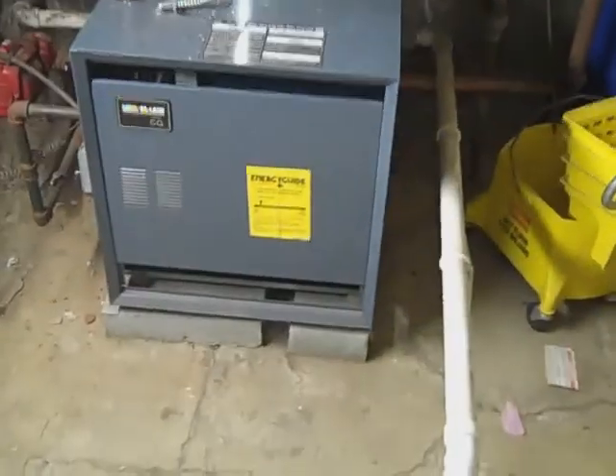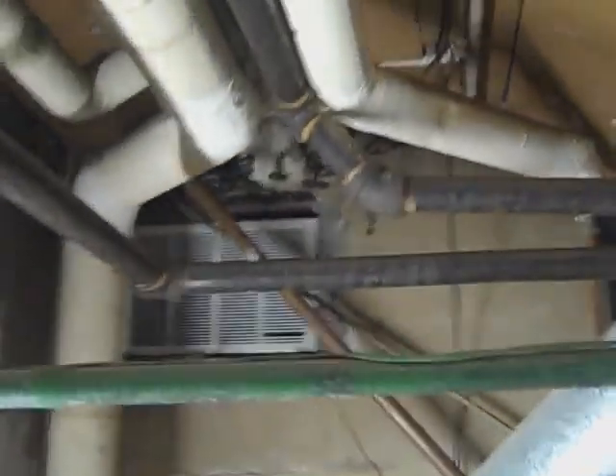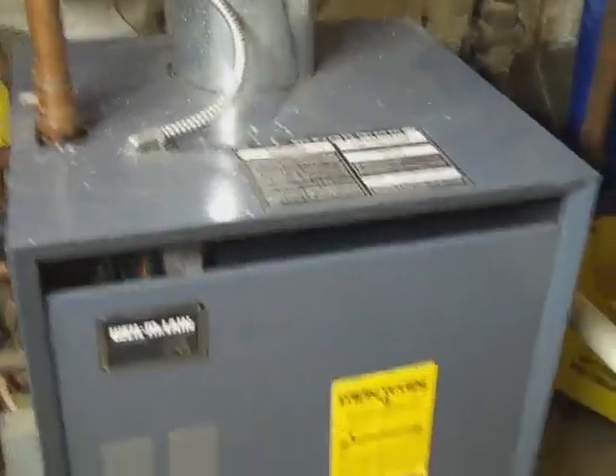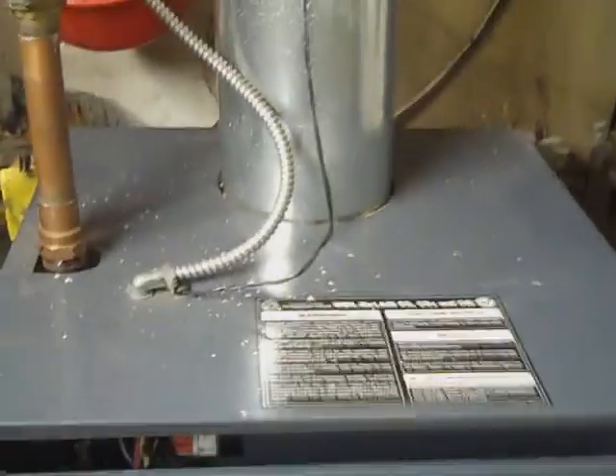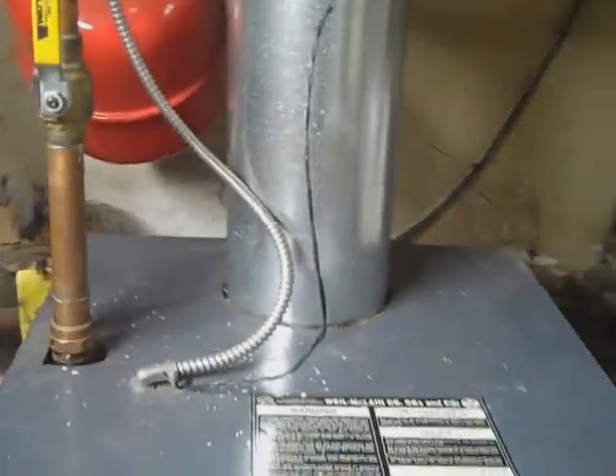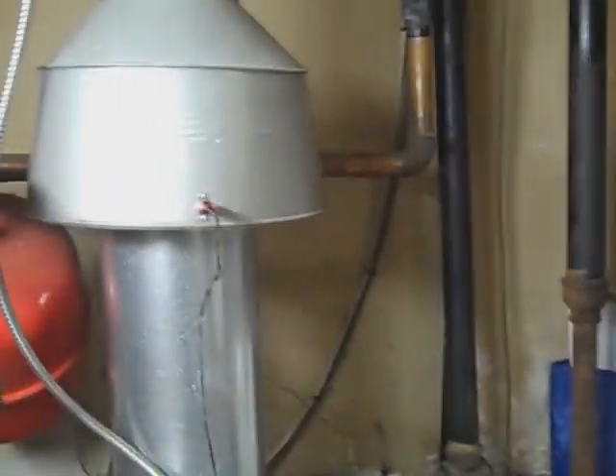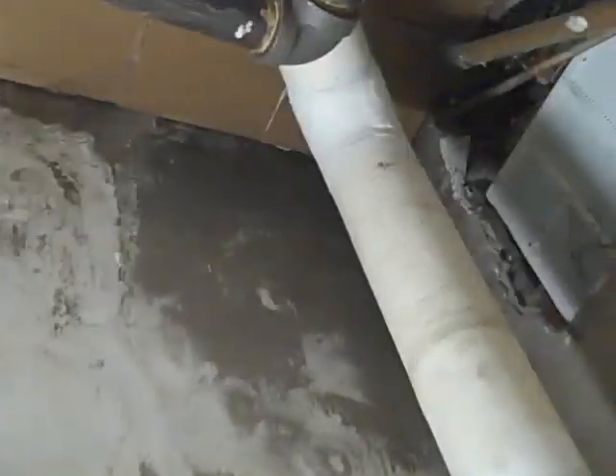You can see there's the boiler. Above the boiler, this is a vent. This vent is actually needed for the HVAC system. See, above the vent there are also holes. What this boiler needs is really controlled ventilation, not uncontrolled ventilation, which is what it's getting right now. So determine how much air it actually needs, get a pipe in here with a fan that delivers that air when it's running and does not deliver air when it's not running, and then close down all these things that just deliver air uncontrollably.